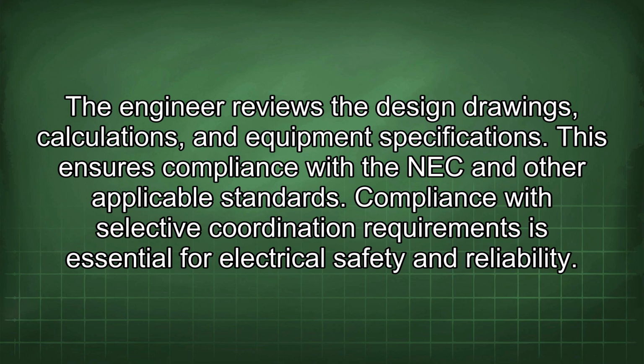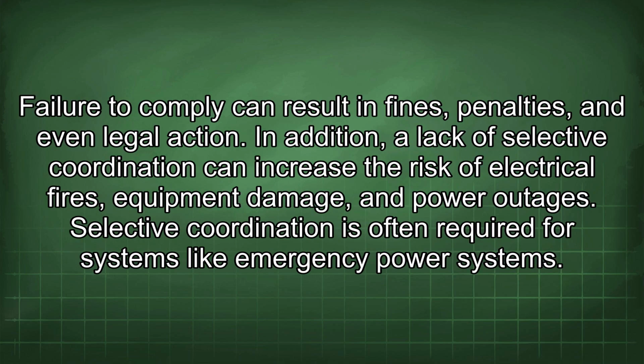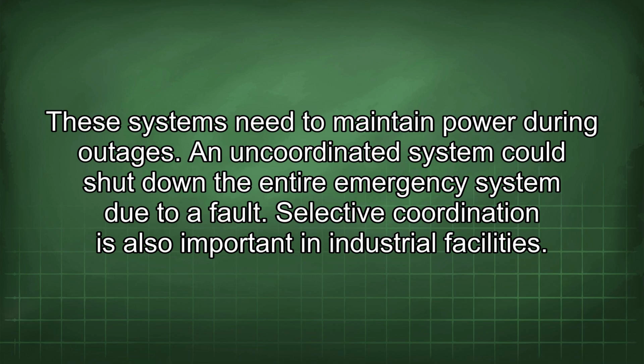Compliance with selective coordination requirements is essential for electrical safety and reliability. Failure to comply can result in fines, penalties, and even legal action. In addition, a lack of selective coordination can increase the risk of electrical fires, equipment damage, and power outages. Selective coordination is often required for systems like emergency power systems. These systems need to maintain power during outages. An uncoordinated system could shut down the entire emergency system due to a fault.